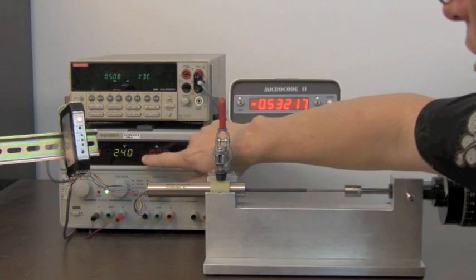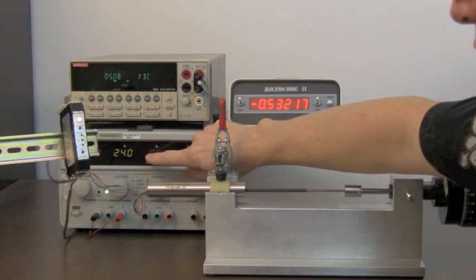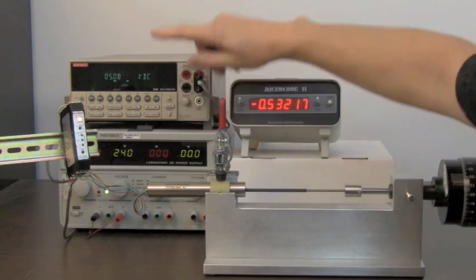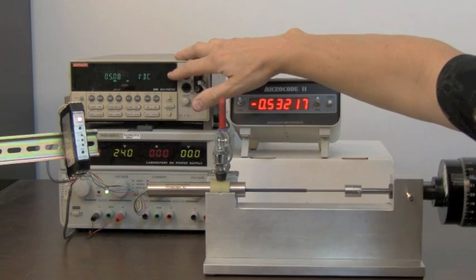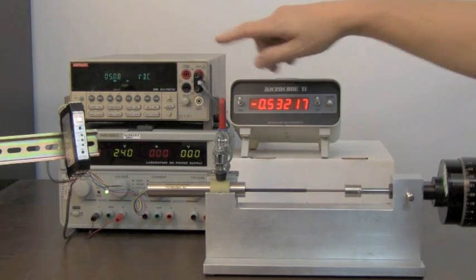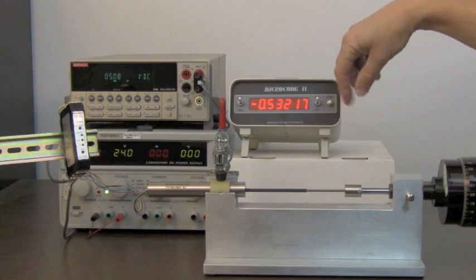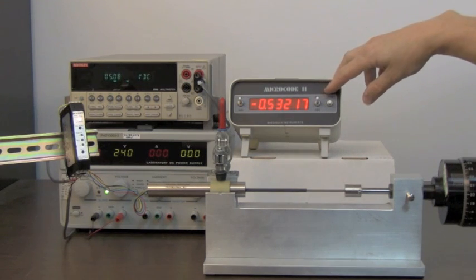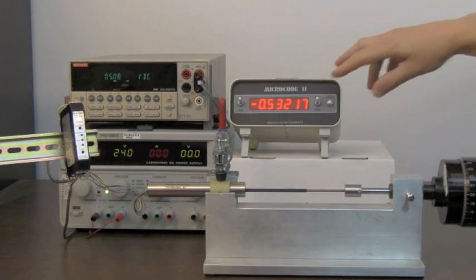For this demonstration, we will be using a regulated DC power supply set to plus 24 volts DC, a digital voltmeter, and a microcode 2 digital micrometer with readout. The head of the digital micrometer is attached to the end of a custom test fixture in which the LVDT will be positioned during calibration.